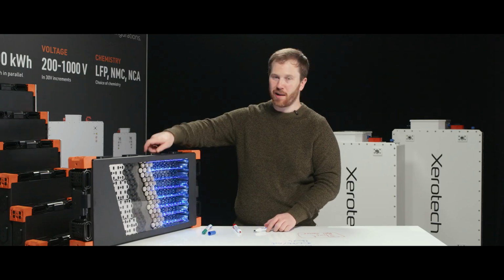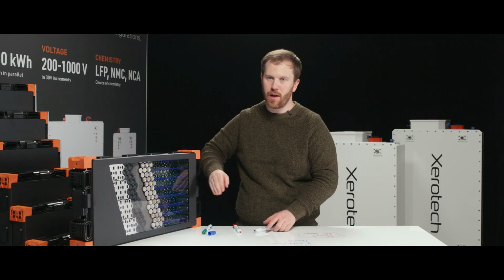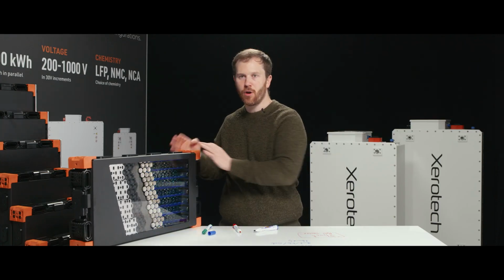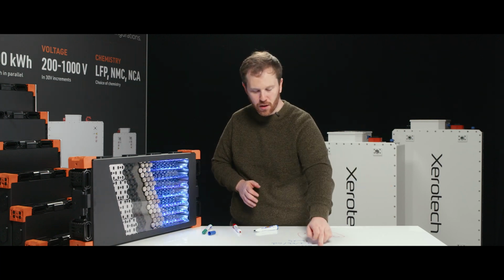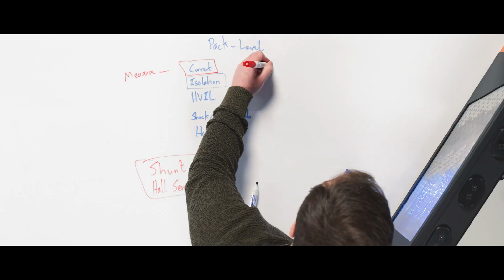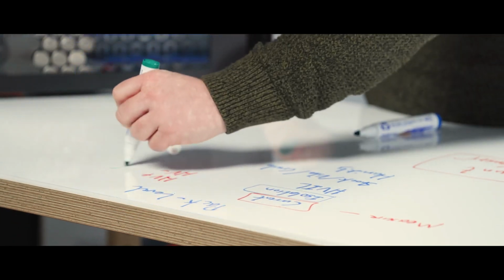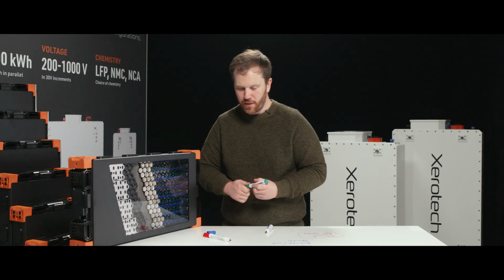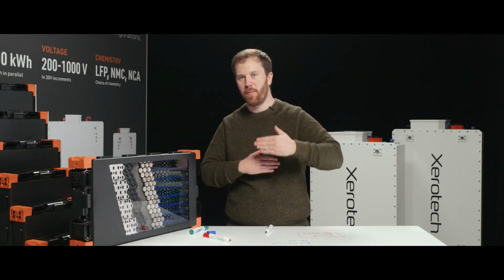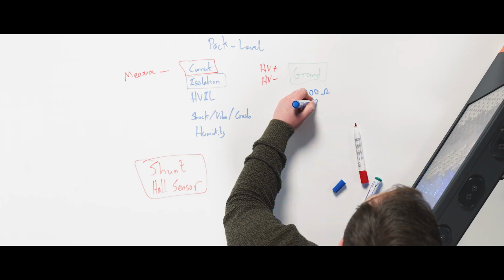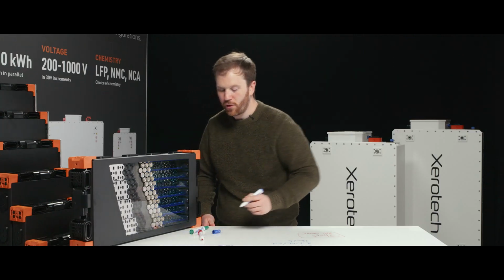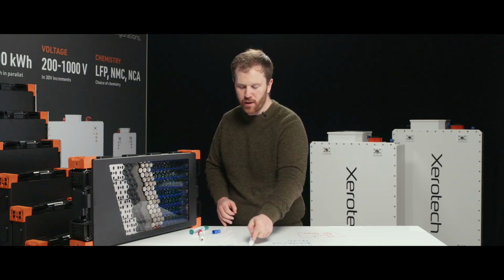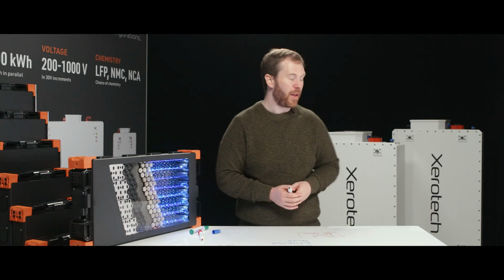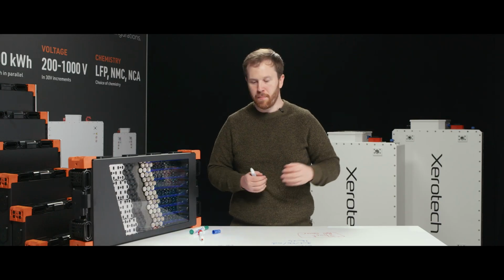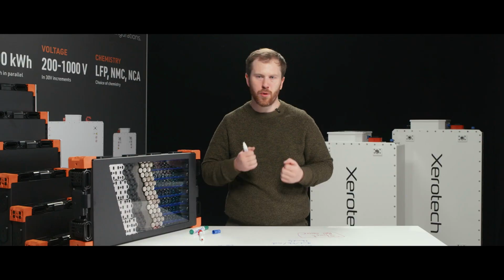So with a battery, it's got a plus and a minus, high voltage plus, high voltage minus. Both of these are floating with respect to the chassis or ground. It's different to the power in a building. So what isolation is doing is it's checking between HV plus, HV minus, and ground. It's making sure that the resistance between these things is high. You want to make sure it's above a certain threshold, and depending on the standard, you're looking at about 100 ohms to 500 ohms per volt. So basically, you need to be a few 100,000 ohms of resistance between each of these for your system to be good. So there's special sense circuits happening inside of that BDU or in other system packs, measuring between HV plus and ground, HV minus and ground, to ensure we have isolation.